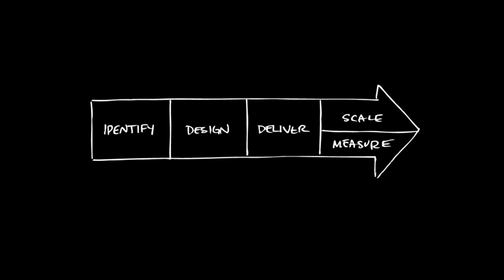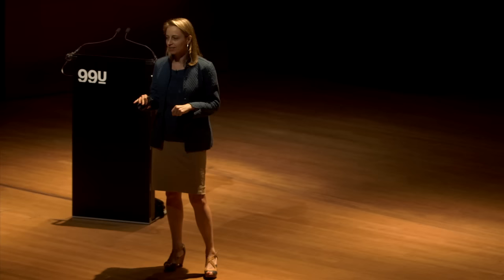So I thought I would jump out and talk about what we see as our design process. We take a very systems approach to design. And many of you, being designers, will say, this is a very oversimplified design process, and I agree. But I just want to walk through how we do think about it. The first stage is identify. And this is understanding, of course, your users, understanding your need, understanding the landscape. What would be the price point for a product like this? What's the ambient temperature? Many medical devices that get regulatory approval only have to work up to 35 degrees C. That's much lower than some of the places where we work. So understanding that whole picture.